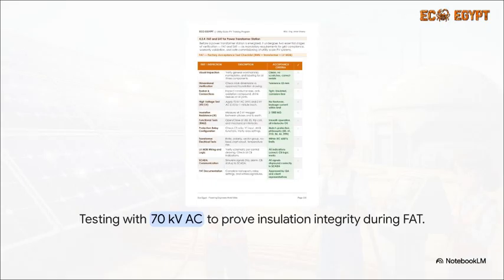Take a look at this actual FAT checklist for a power transformer. Engineers take this stuff incredibly seriously. During these dielectric tests, they are literally blasting the equipment with 70 kilovolts of alternating current. They do this just to absolutely guarantee that the internal insulation won't suddenly flash over or break down when it faces worst-case electrical stress in the real world.